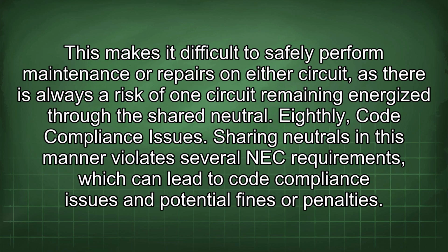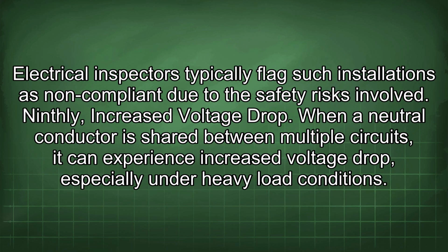Eighthly, code compliance issues. Sharing neutrals in this manner violates several NEC requirements, which can lead to code compliance issues and potential fines or penalties. Electrical inspectors typically flag such installations as non-compliant due to the safety risks involved.